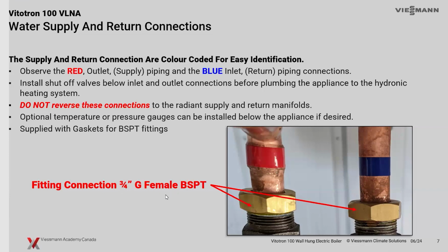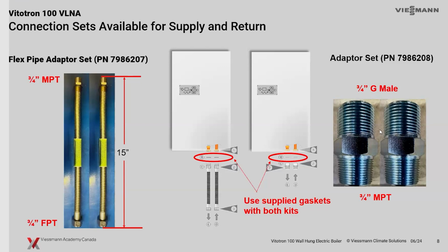This is the exact same concept. These are a G thread, British Standard pipe parallel thread on these. So they're a gasketed connection here. We do have line sets that are available and adapters to go from 3/4 inch to NPT, as well as these 15-inch line sets that are available here as well. We've actually had recommendations. A lot of guys will actually use copper female adapters or copper male adapters, just NPT. As long as you use the gasket, that's acceptable as well. We tend to say avoid using black iron fittings just because there's no flatness to that thread, and you might cut into those little gaskets there. So NPT, copper, some of your PEX adapters, we've used NPT directly to the G thread here. However, if you want to use an actual G thread connection, we do have some of these adapters that you can add on or order to make that transition between the G and the NPT here.